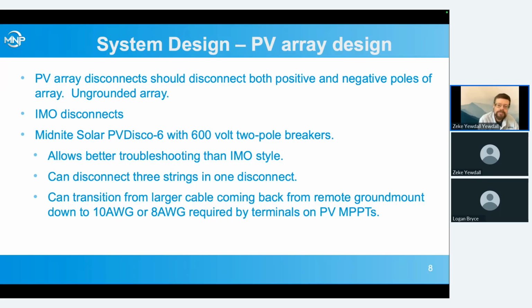I don't like that they're in a plastic box most of the time. And if you've mounted that on, say, the exterior of a house, I just question long-term holding up to UV. But they work good. The thing I prefer is using the MidNite Solar disconnect box. It's got the little red handle on the cover that operates the breakers. And using the new 600 volt 2-pole breakers, you can separate the 2 poles and use one for the negative and one for the positive.